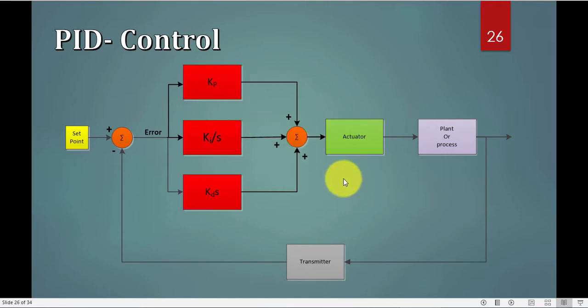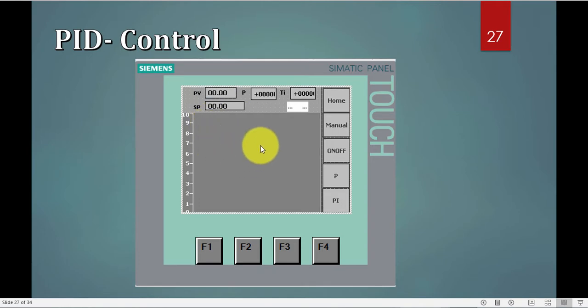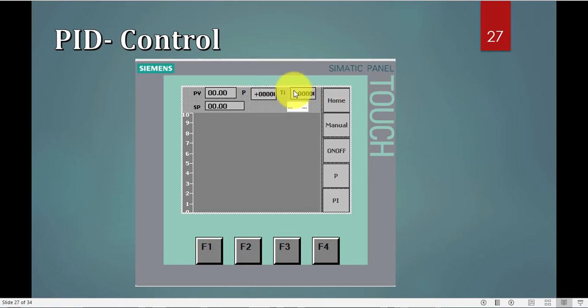This is the HMI screen I created for the PID Compact. I still have the setpoint, the PV, and the trend. New additions include the value of the P control or KP, and the value for TI or KI of my PID Compact. Finding those values is really all that tuning a loop is about — finding the correct values so that my PLC will behave correctly.